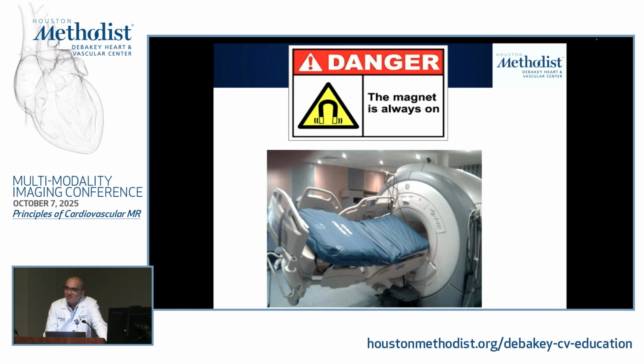Right here, this I think you need to recognize. There's a saying I always say: the magnet is always on. What that means is that Sunday night, the scanner is turned off, all the lights are out, nobody's around. The magnetic field is still there, right? If it's a 1.5 Tesla, it's still a 1.5 Tesla magnetic field. That doesn't ever get turned off, right? So as a result, you cannot take some metallic object into the room without knowing what it is.